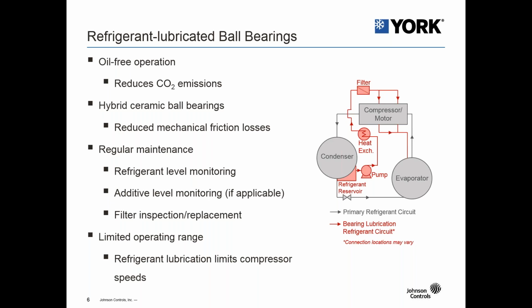So if we look to the schematic to the right and look at the lubrication system for the refrigerant lubricated bearings, it's very similar to what we were looking at on the oil lubricated system. So we still need a reservoir for the lubricant. You still need a pump to create that pressure differential.